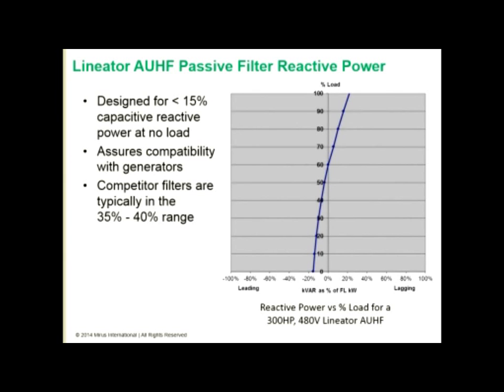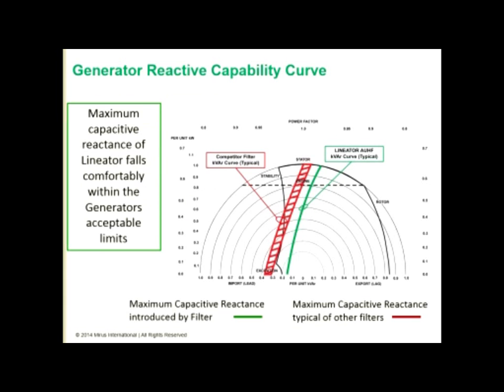Competitive filters are much higher levels, typically in the 35 to 40% range. And that's a problem because generators do not like to supply leading power factor loads. They're much better at supplying lagging power factor loads. And this graph shows a typical reactive power capability curve of a generator.